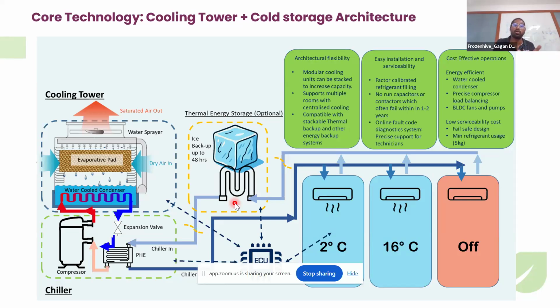For example, if you want your cold room purely on solar, you'd probably need a 16-hour backup, since there's sunlight again the next day. But if you want backup because of unforeseen power outages, maybe due to heavy rain with frequent power cuts often observed in rural areas, you can have a much larger energy backup system. That gives you considerable time—in this design, it's about 48 hours, which is 2 days, so your temperatures are sustained for the next 2 days without using any generators.